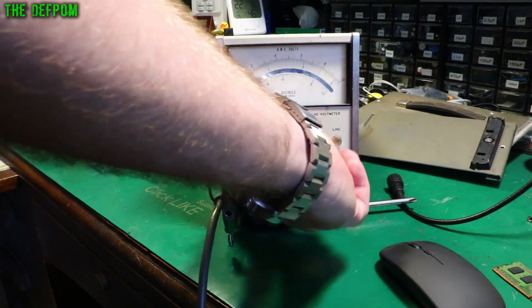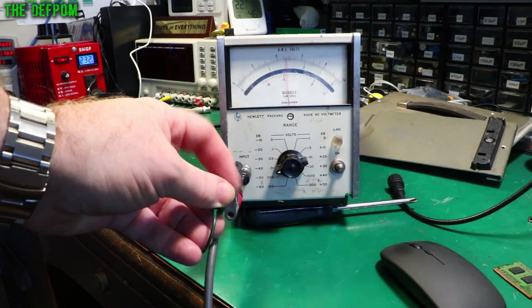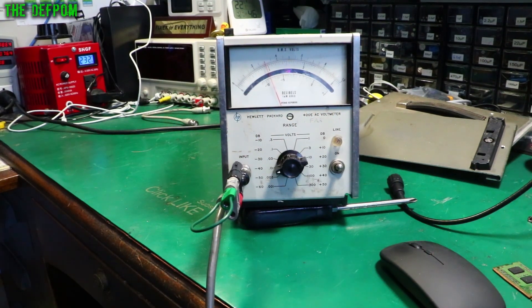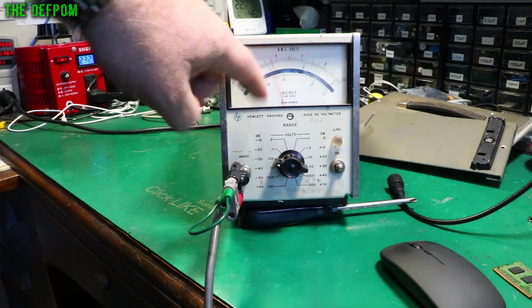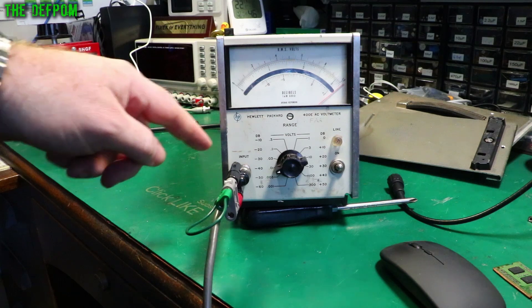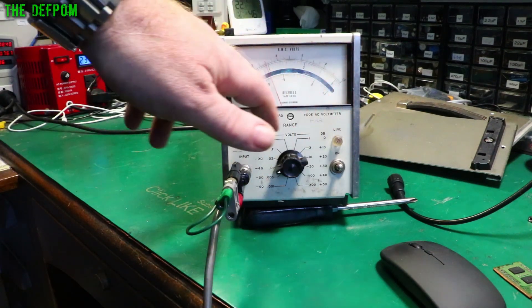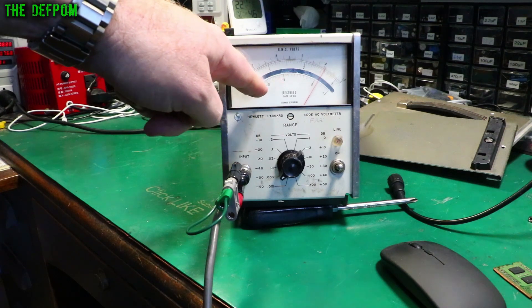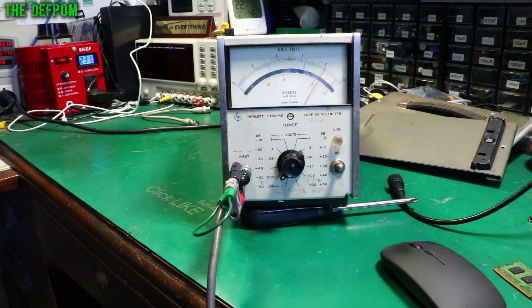Let's do one millivolt. Yeah see these bottom ones are definitely reading much higher. If I try sticking the grounding on, there we go. Let's put the guard on the negative side. That might be helping it actually. Let's go back to 10 millivolts. Should have put it out first. So 10 millivolts again. There we go, that's getting better. So it's almost on one there, that's with the guard connected. It extends to the other end as well. And this one's reading slightly over. So it could be some electrical noise causing that problem. One millivolt, it's in the 0.1 range. So it should be sitting down here and sitting much higher. So it's sitting way up there. So I think there's probably electrical noise. I don't have the covers on, maybe putting the covers on will help it. But it is at least working.